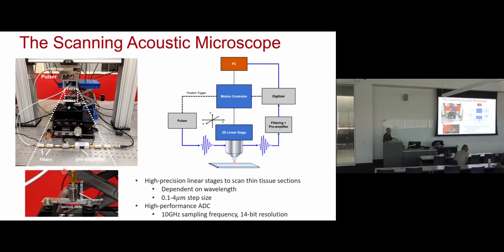The concept is easy, but putting this together is a complete engineering nightmare. So first, it requires very precise motor stages. We're stepping in fractions of micrometers. Any vibration will create problems. Even the temperature in the room has to be controlled and measured. It requires extremely fast electronics. So if you are exciting a transducer at a gigahertz, you need to sample it at least at 5 gigahertz. So you need to buy very specialized digitizer cards.